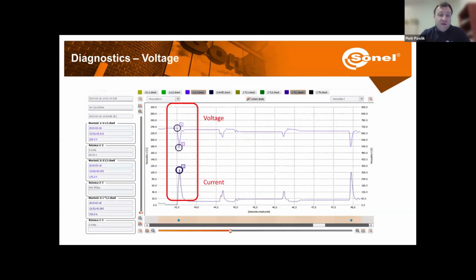Next things will be voltage dips. So when we have higher power chargers, they will cause voltage drops in the mains, which may cause a number of problems with functioning of devices in conditions of reduced voltage or cause decrease in their efficiency. In addition, in extreme situations, the permissible voltage level set by regulations may be exceeded. So when we connect a lot of loads at the same time, the voltage may drop.